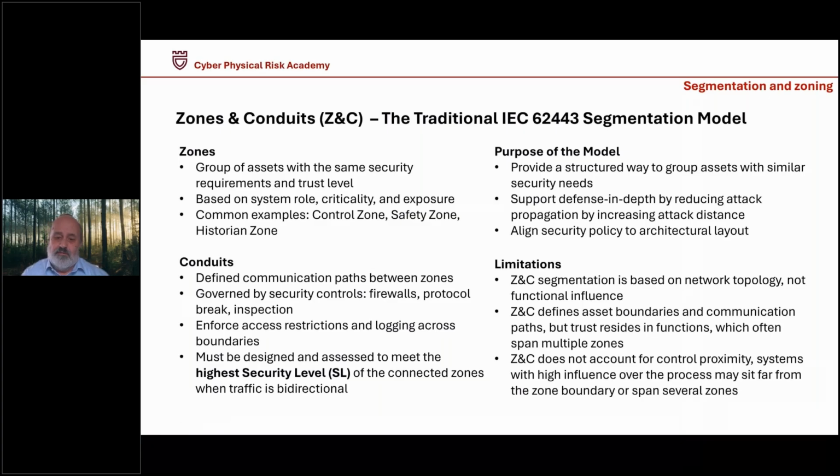So an operator station has kind of the highest control proximity, because from there I can manipulate the valve, I can impact the process and do things. And a node somewhere else, like a domain controller, to give an alternative, has a very low control proximity. It does not really directly impact the process.